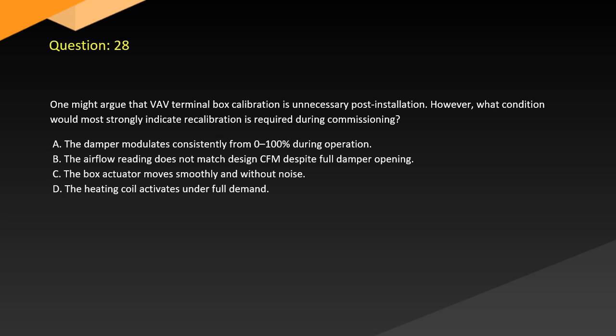Question 28. One might argue that VAV terminal box calibration is unnecessary post-installation. However, what condition would most strongly indicate recalibration is required during commissioning? A. The damper modulates consistently from 0 to 100% during operation. B. The airflow reading does not match design CFM despite full damper opening. C. The box actuator moves smoothly and without noise. D. The heating coil activates under full demand.